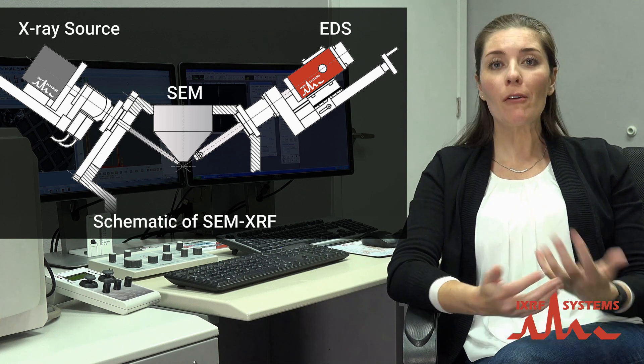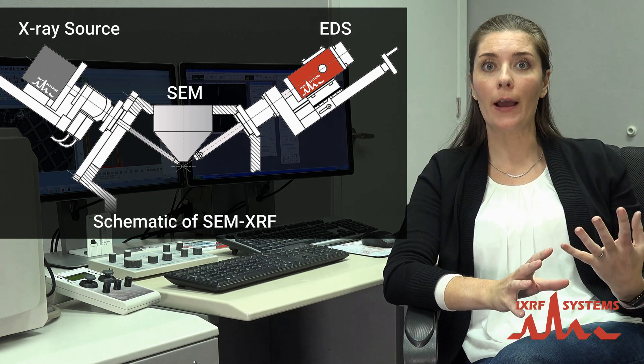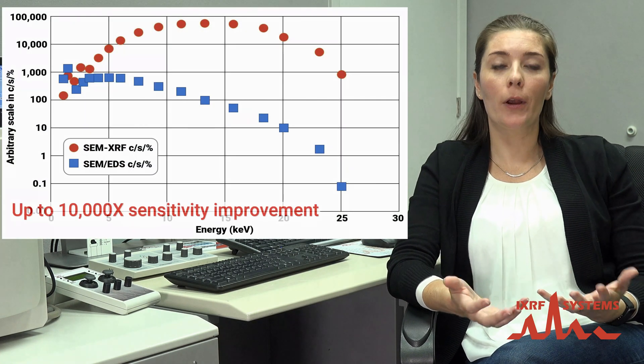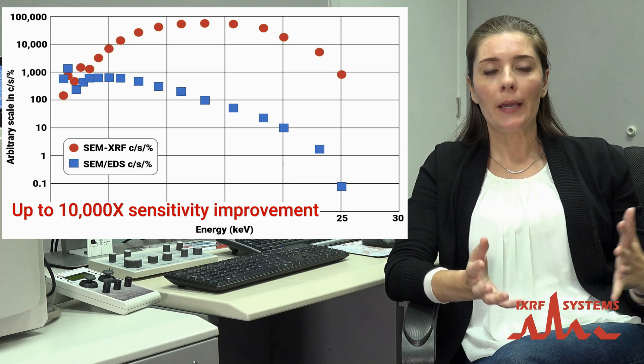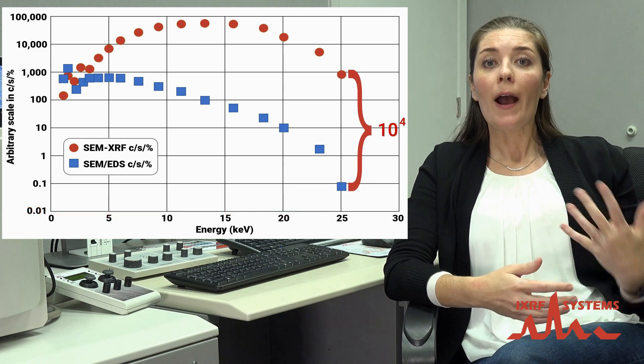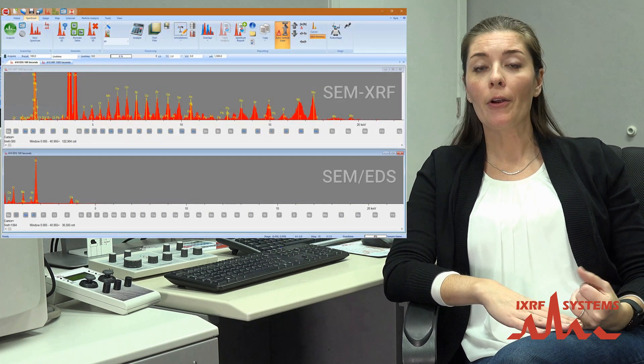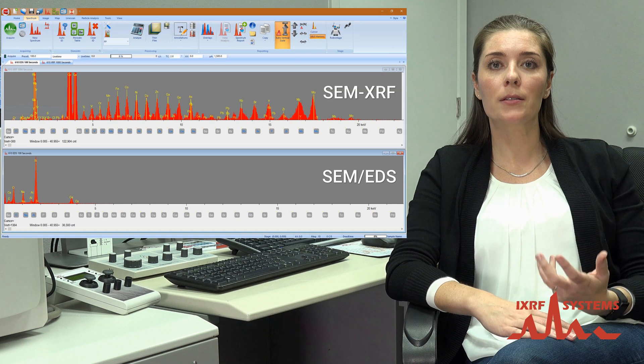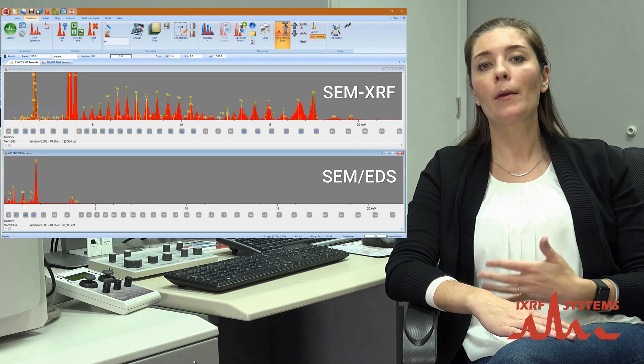So how can someone using an SEM with EDS get even more from their system? With your normal EDS system, you're using the electron beam of your SEM to get your elements. But what we can do is add XRF to the SEM — you may have heard of bench top XRF or handheld XRF. That actually gives us a lot more information. With your E-beam, you're only able to get certain elements and certain peaks. With XRF, we're able to get some of our heavier elements, resolve peak overlaps, and see trace levels of elements that we're not able to see on EDS.